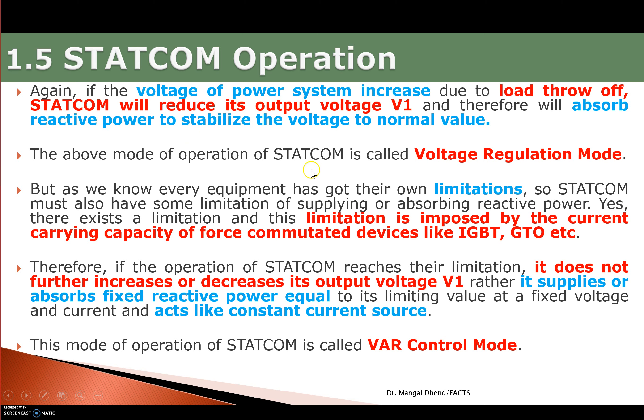The above mode of operation of STATCOM — where reactive power flow depends on the magnitude difference between V1 and V2 — is called voltage regulation mode. There are two modes of STATCOM: the first is voltage regulation mode and the second is VAR control mode. In voltage regulation mode, when V1 and V2 magnitudes differ, STATCOM either supplies or absorbs reactive power accordingly. Do not confuse VAR control mode with voltage regulation mode.